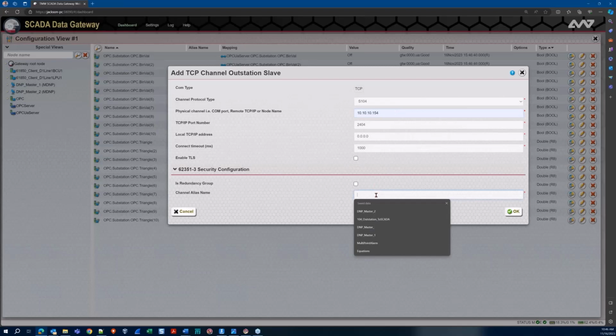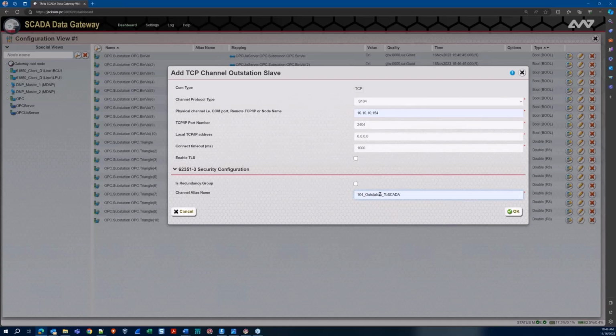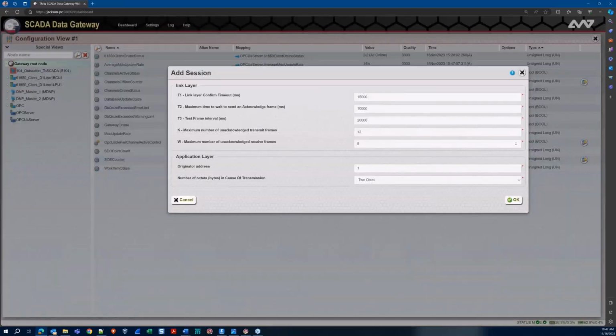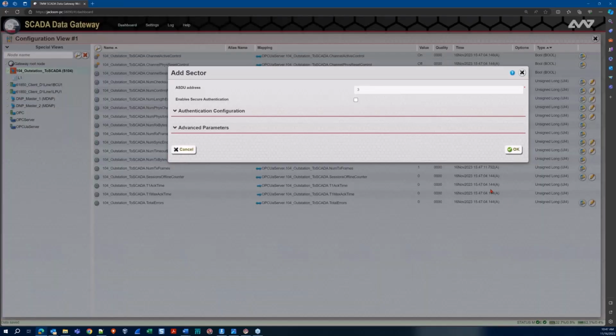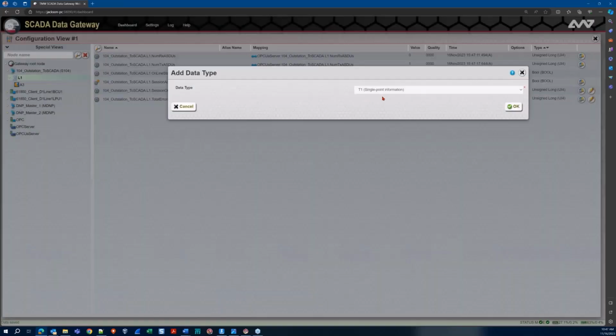For a channel name, it seems to be remembering the names I used in my trial run, so I'll go with 104 Outstation to SCADA — 104 indicating the protocol, outstation clarifying that the data is coming out of this device and being passed up to my remote SCADA system. The rest of these settings I can keep as default, and I'll just click through. I can keep the security parameters the same; you might need to adjust them on your particular device, but for now everything is good.